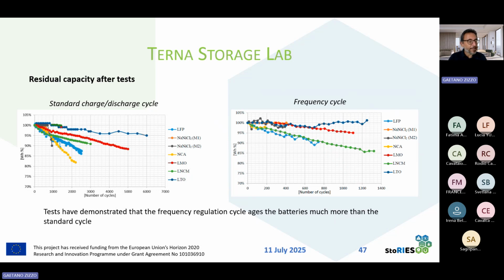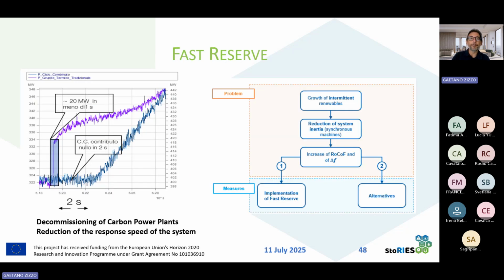Frequency regulation is a very important function for the security of the system, but remember that the life of batteries can be reduced faster than if they are used for other applications like energy arbitrage, load following, or peak shaving.